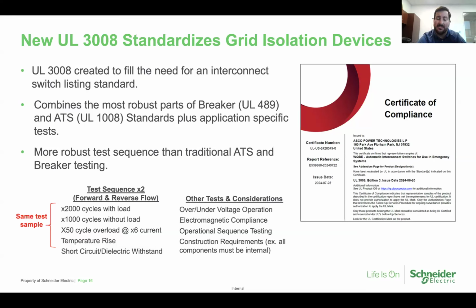Meanwhile, UL 3008, most of those tests actually have to happen on the same sample. So each time you go into a test, the sample is more beaten up from the previous test already. So it's a much more robust and difficult standard to pass, which results in a more robust product and a higher level of reliability out of the product. So that's part of the reason why.